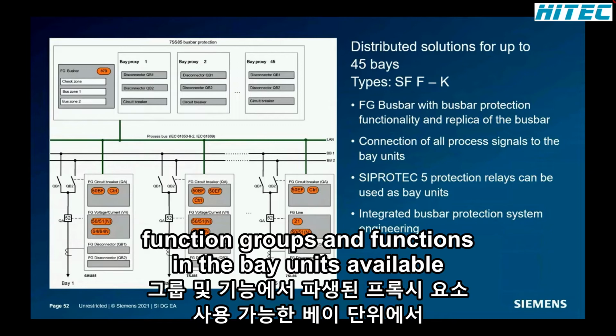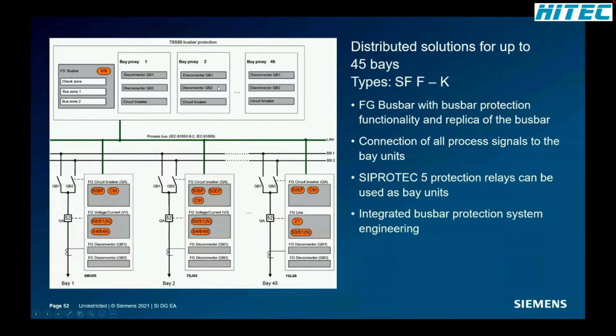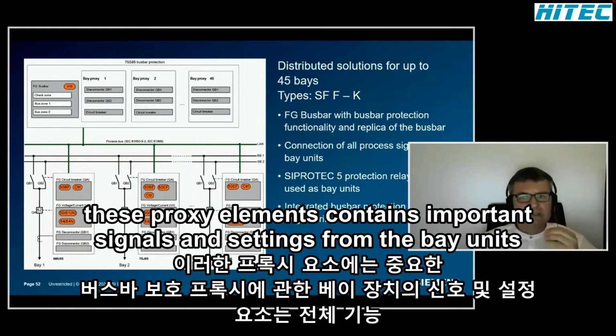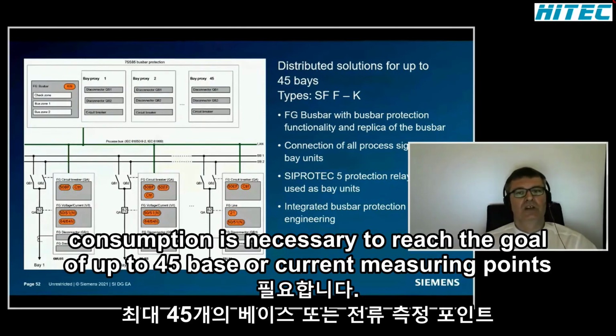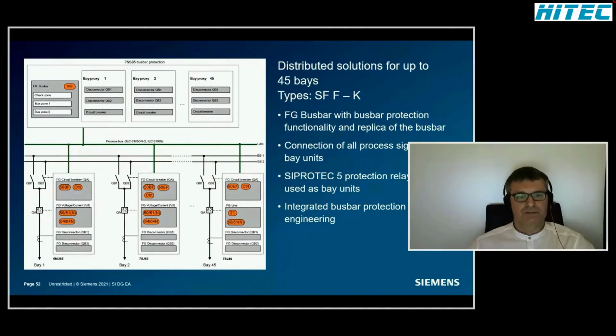In the 7SS85 center units are only proxy elements derived from the full function groups and functions in the bay units available. These proxy elements contain the important signals and settings from the bay units regarding busbar protection. The proxy elements need a reduced amount of memory compared to the full function groups and functions in the centralized 7SS85. This reduced memory consumption is necessary to reach the goal of up to 45 bays or current measuring points.